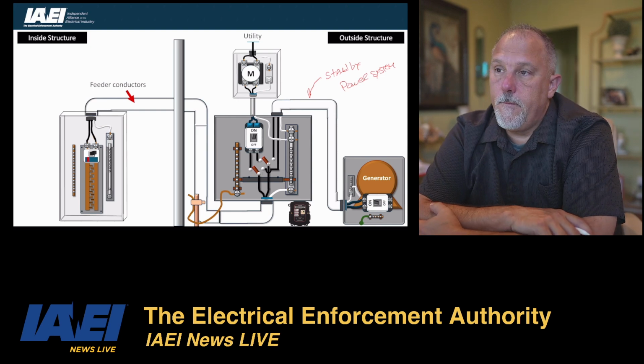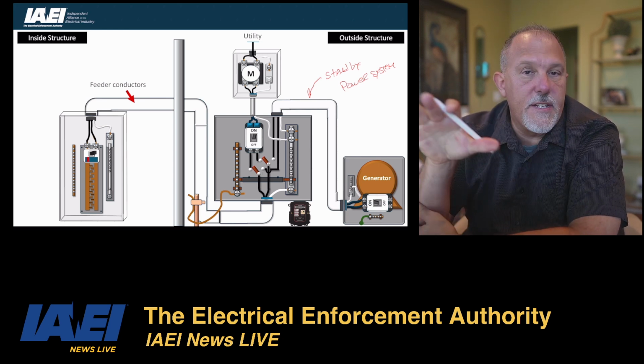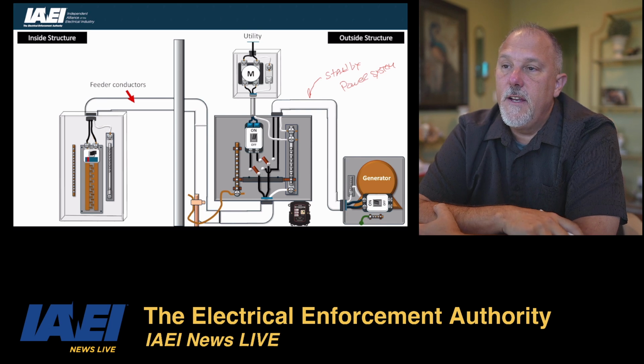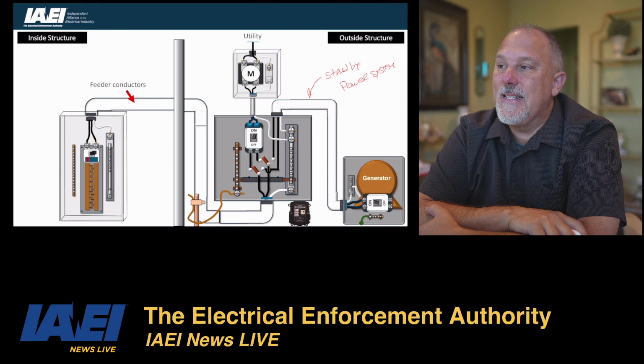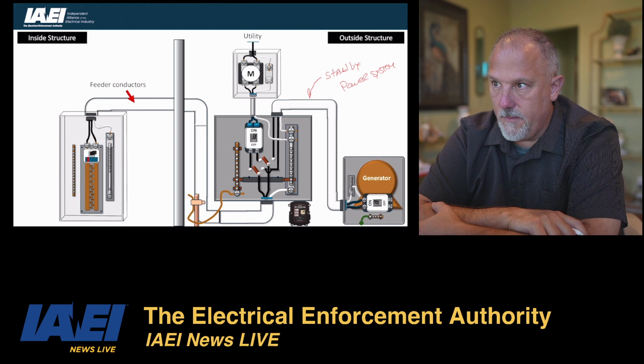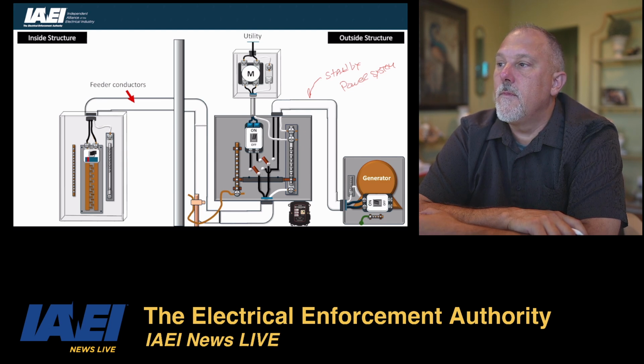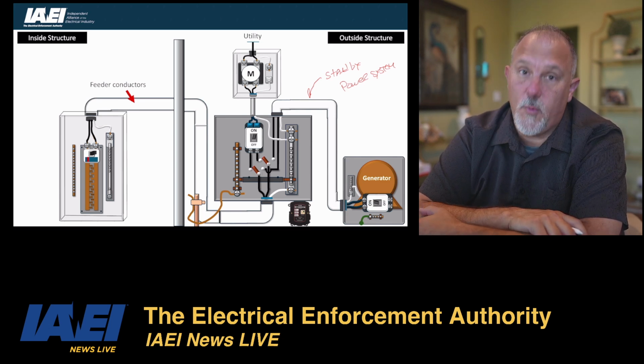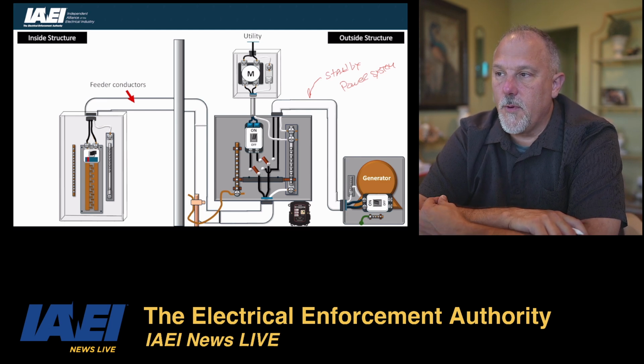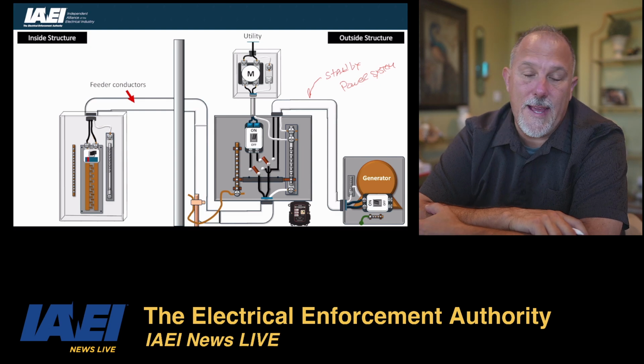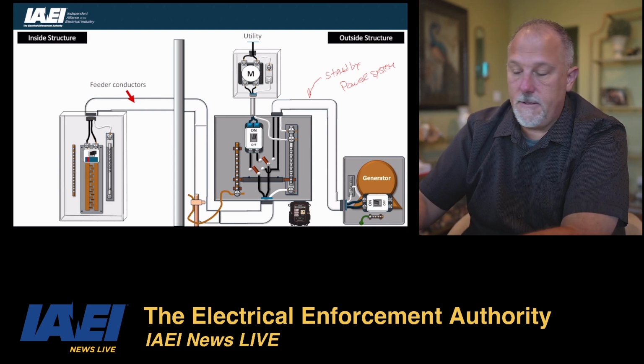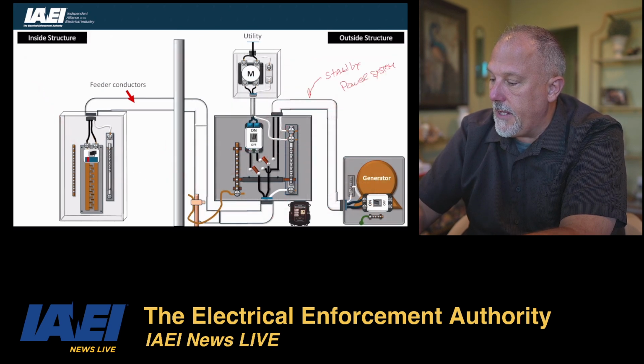So what 5 says, conductors used to supply, and I'm just going to focus on the standby power systems: conductors used to supply standby power systems, if provided with service equipment and installed in accordance with the requirements for service entrance conductors. So what that meant was that this had to be service equipment.